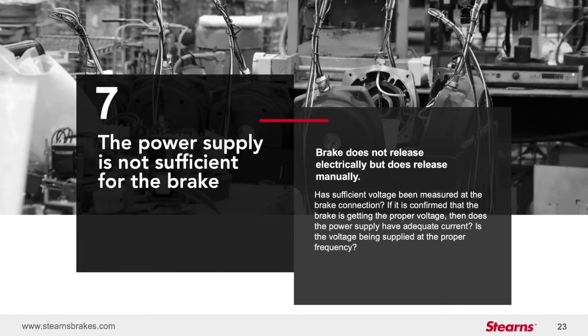So the first thing I suggest is that you need to measure voltage at the brake connection. Confirm at that location where the power leads connect to the brake leads that you're getting full voltage. Now, there can be several reasons why either you're getting low voltage or inconsistent voltage, or voltage just cuts out, but some of them can be as simple as a bad connection, a broken wire, a sticky contactor. These can be reasons why you're getting inadequate voltage at the brake connection, and thus the brake is not getting power. Another thing you want to check is, does the power supply have adequate current? You need a certain amount of current for inrush to release the brake. You need a certain amount of current to keep the brake released and hold it released. So you need to check if you have adequate current.